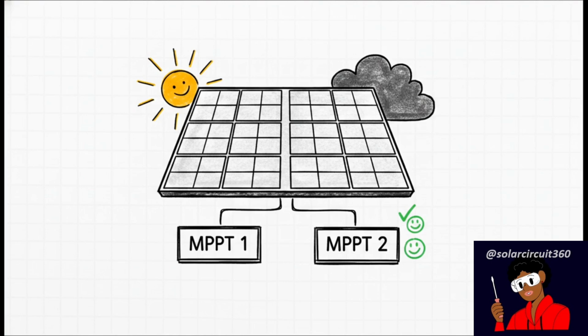All right, section 4, why choose dual MPPT? Rather than trying to force a 10-kilowatt array through one single bottleneck, we divide it. We split it between 2 independent MPPT charge controllers. And the benefits here are huge. First off, you get a higher overall solar capacity. You will also achieve significantly better shading tolerance because each controller optimizes its own specific set of strings. You get independent array optimization, and crucially, this is the big one, you reduce the stress and the heat load on each individual controller. It just creates a much more robust system overall.